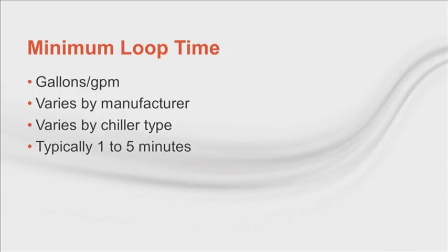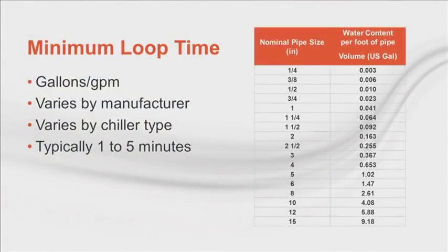We've seen requirements on chiller mechanical specifications anywhere from 1 to 5 minutes. If the system is small, the volume of water in the system is often too low, and you'll need to add volume. The easiest and most common way to do this is with a buffer tank on the inlet side of the pump. The other option is to reduce the flow rate, which has the same effect as extra volume on the loop time. How do you know how much loop volume you have? The chiller report will tell you how much water is in the chiller itself, then use this chart for the volume per length of a certain diameter pipe.